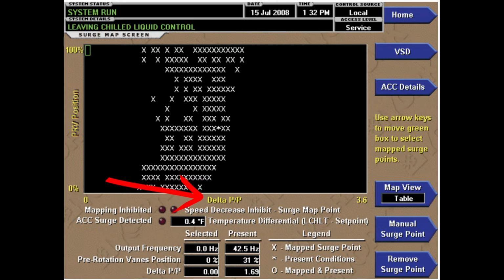It's just a form of compression ratio, and this is one of the ways that York uses it in mapping the surge map. Now, I'll get a little deeper into this while we're here. One of the things you have to be careful with is this map will clutter up. York does not recommend clearing this map, and they have gone out of their way to make it so that unless you're already trained and know how to do this, getting to this point is quite difficult.